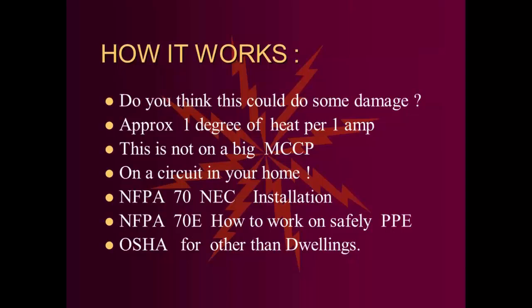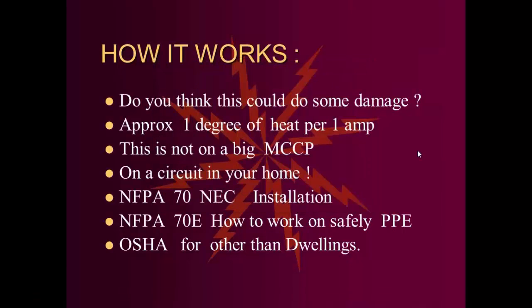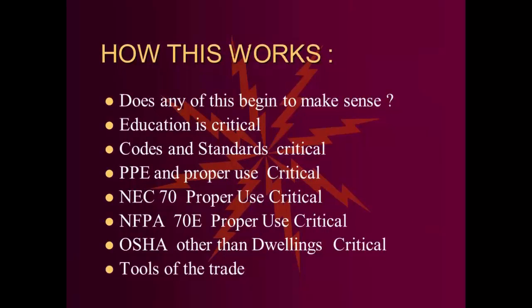NFPA 70, the National Electrical Code, will tell you how to install that circuit correctly: the size of wire, the size of overcurrent device to interrupt when something like that might happen. 70E will tell you how to work on that circuit safely if it's in a commercial location. Do we have 120 volt circuits in commercial locations? Absolutely. And then, of course, the OSHA standard is for other than dwellings, but it tells us to be safe.